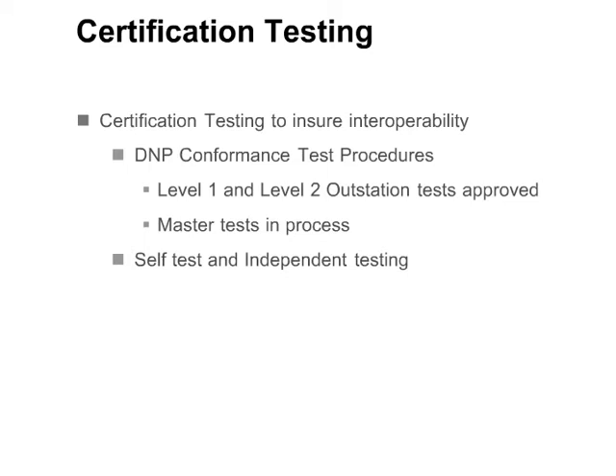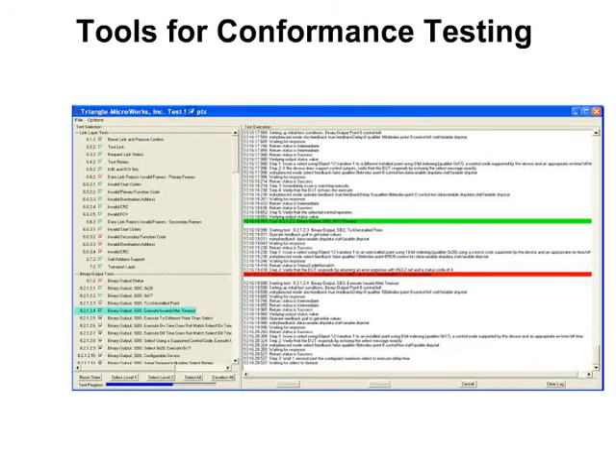The DNP3 conformance test procedures are currently approved for subset Level 1 and subset Level 2 outstations. Conformance tests for master stations are currently under development. Vendors may self-test their devices, or they may have an independent test lab perform the conformance tests. The DNP user group website lists devices and their certification status. An end-user may opt to specify that self- or independent testing is required of the equipment used in their networks. The Triangle Microworks Communication Protocol test harness supports an optional module that automates the conformance test procedure. This screenshot shows an example of this module, with individual tests shown down the left and the right-hand column showing the current status of the testing.